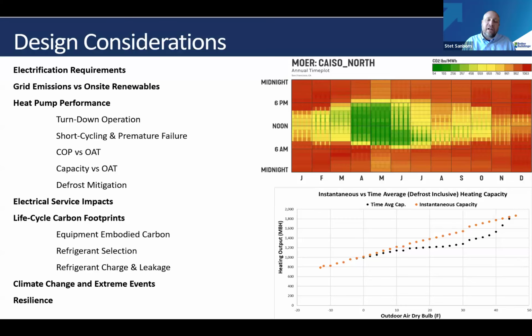When we approached this project, there were a number of things we were trying to balance. Obviously, we were told it's got to be all electric. We want the lowest emissions profile possible. We're also going to be doing an on-site microgrid on our campus, so we want to make sure we're taking advantage of that. And in our own research and through our work with ASHRAE and the Better Climate Challenge, we know that heat pumps can be challenging when they're working at part load conditions or have to turn down. There are a lot of premature failures from short cycling heat pumps. And we know that we can design a heat pump system better if we combine it with thermal storage. So there are a lot of benefits to pairing the two together, not just for footprint, but also for cost.